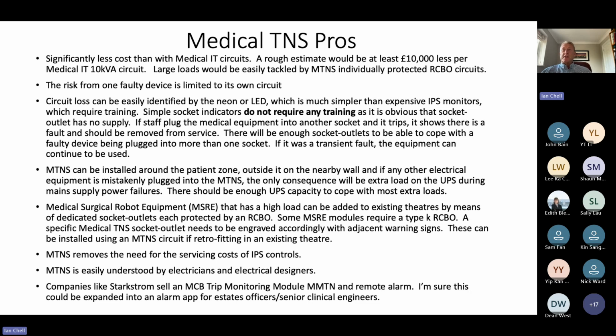by the third time, that will tell them, okay, yeah, there is a fault. Let's not use this anymore. If it was a transient fault and they plug it into another socket, end of problem. And estates can come back and reset that one circuit.